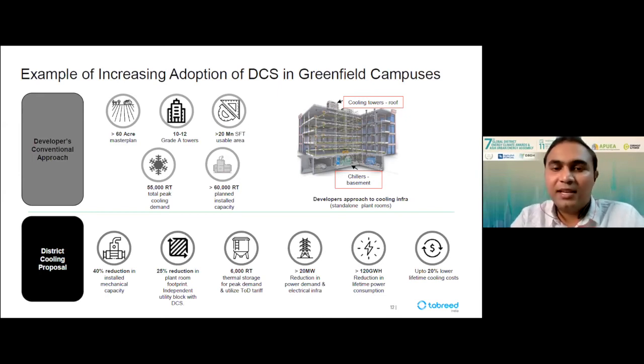On the top, what you see is a conventional approach a developer used to follow maybe in the last decade, where, say, suppose this is a live case where Tabreed has been developing in the country - for a very large campus area with mixed use or commercial purposes, the developer used to go by a conventional model and install more than what was needed. Right now, the majority of developers in the country are shifting to the district cooling model, where rather than installing a higher capacity, they try to integrate the entire campus cooling requirements in a single utility plant, which is a district cooling plant, and achieve project diversity benefits of cooling as high as 40% in the installed cooling base.